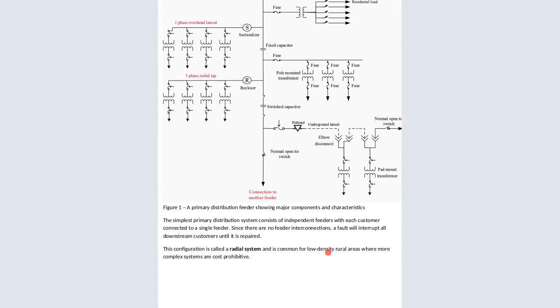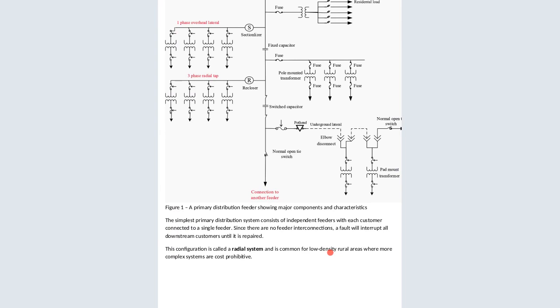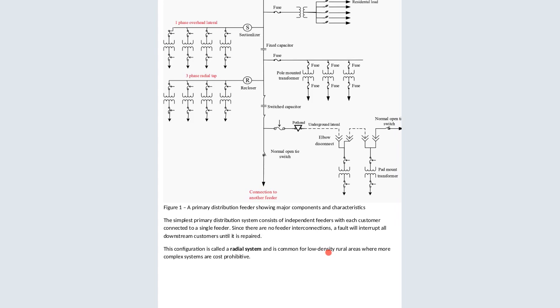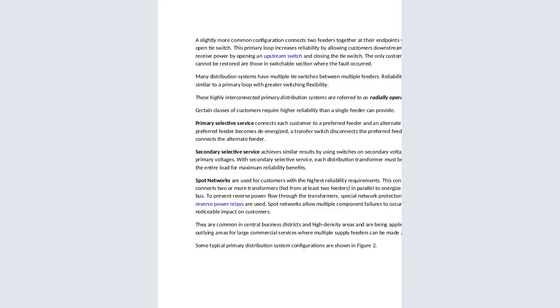The simplest primary distribution system consists of independent feeders, with each customer connected to a single feeder. Since there are no feeder interconnections, a fault will interrupt all the downstream consumers until it is repaired. That is the major problem with that. This configuration is called a radial system, and it is common for low-density rural areas where more complex systems are cost prohibitive. So this type of topology or distribution is normally used in rural areas because of the interconnection problems.